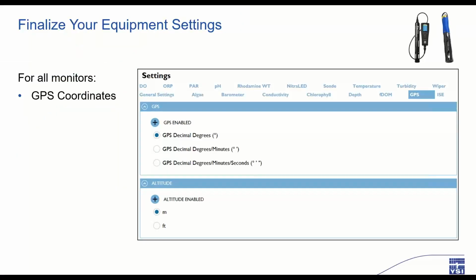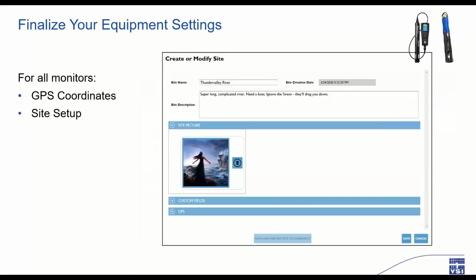There are quite a few different configuration options to choose from, and they all relate to how you want your equipment to record data. For spot sampling, it may be important to have GPS coordinates logged along with your measurements. With technology like EXO and the ProDSS, GPS is built into the handheld and can be activated in the settings menu. Once activated, each recorded data point is tied to the associated GPS coordinates in the exported data files.